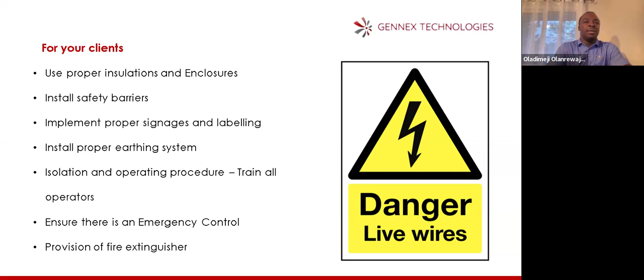Then preventing fire and explosion, good designs and cable sizing. Cable sizing, most importantly, because I know some of our installers come short on cable sizing. I don't know, maybe because we don't know why, or because we're trying to cut costs. But most importantly, areas where fire comes in the most is when cable gets hot, and they get hot to a point, they catch fire. They burn and they catch fire. And if there are flammable materials around that place, it catches fire as well. So proper cable sizing, good design is important to avoid fire and explosion.